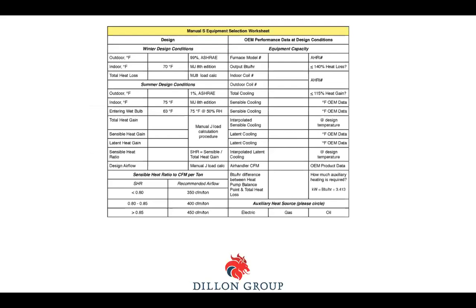And then there's a Manual S equipment selection worksheet. I built this one myself off of ACCA's documents. I just cleaned it up a bit for some work that we were doing with some other clients. Basically it's like, what does the load calculation say? That's the left-hand side. What does the manufacturer's performance data at design conditions say? That's the right-hand side. And then you find a system that meets the design, and all those boxes on the right-hand side match the design, or you can be slightly over or slightly under. But it makes it pretty easy to say, this system does not work, or this system will work. This coil combination will be awesome.